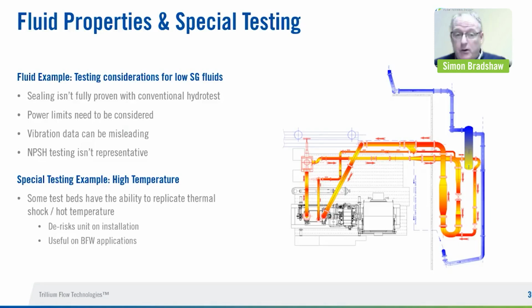Finally, an example on high temperature testing. Massimiliano mentioned this earlier. There are sometimes where we need to test at high temperature to validate that the pump performs acceptably in terms of handling that high temperature, in terms of thermal expansion, in terms of thermal shock. And there aren't that many test loops that can do this. We do have one of those. Next slide.